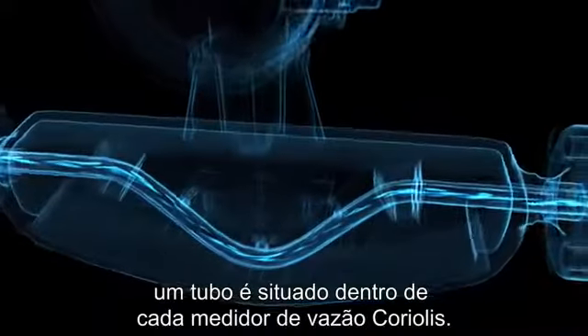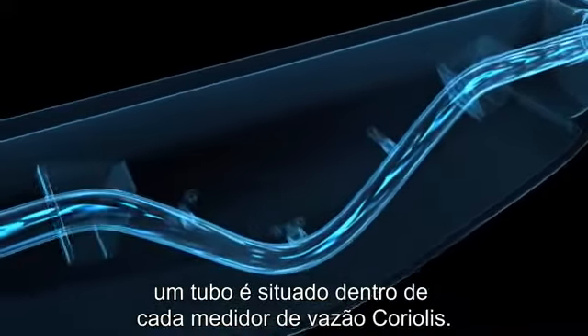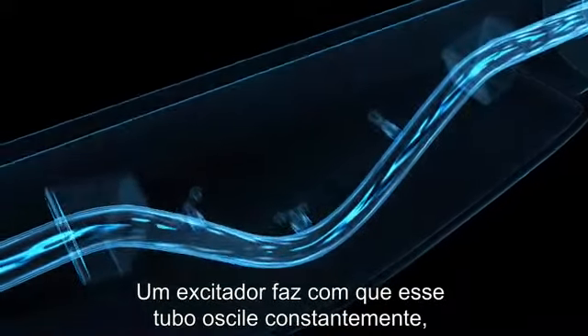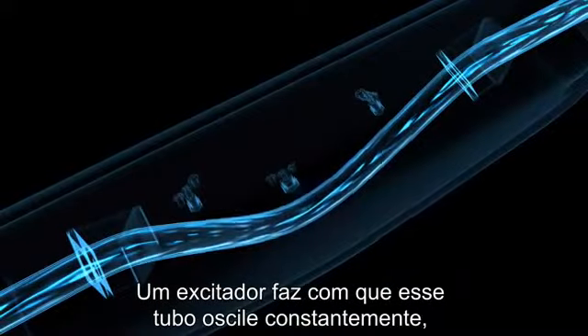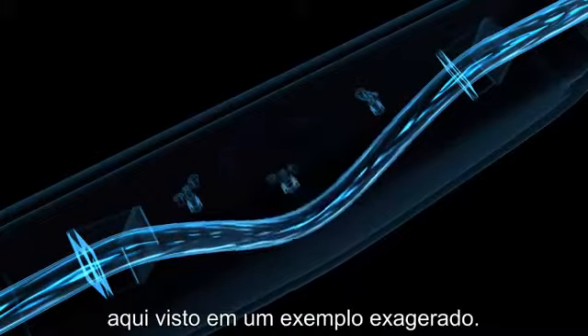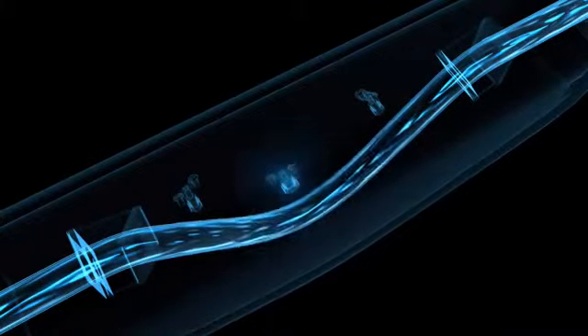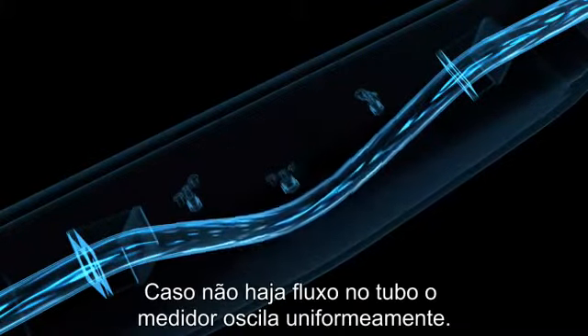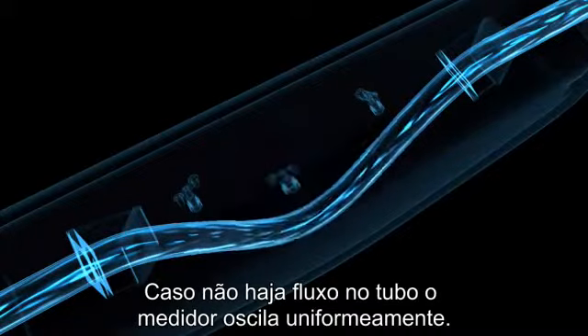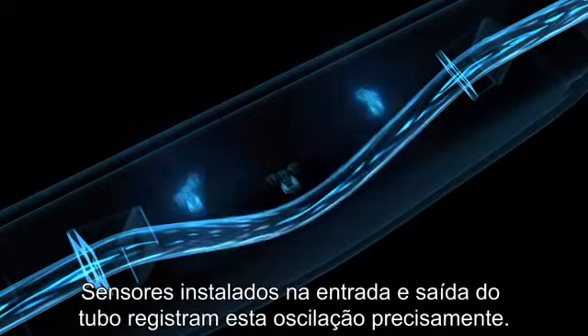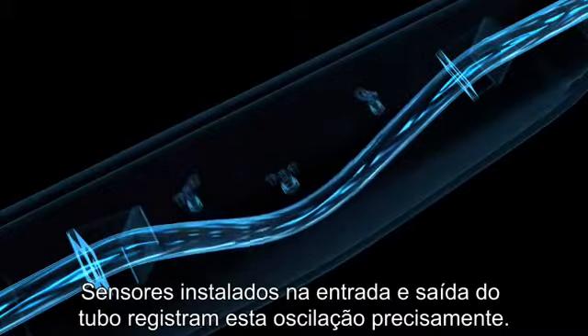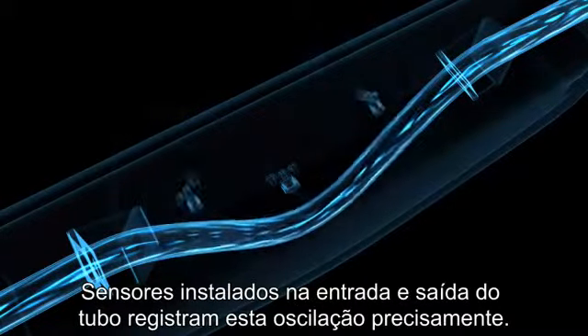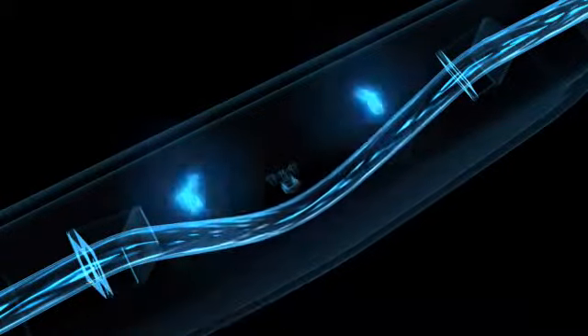A tube is located inside each Coriolis flow meter. An exciter causes this tube to oscillate constantly, here in an exaggerated example. If there is no flow, the measuring tube oscillates uniformly. Sensors are located at the inlet and outlet and register this basic oscillation precisely.